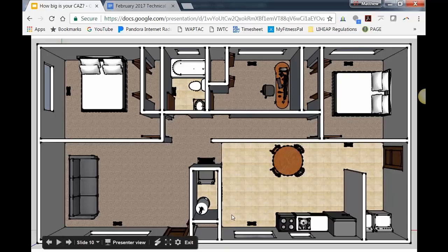So as an auditor, if you're walking into this house for the first time and this is the condition you find the house in, you don't get to modify stuff yet. You first have to do your worst case draft test, right? Because you got to make sure that when you leave tonight that the homeowners are safe. Just unfortunately, that's the burden we carry because of the knowledge we have. So you're going to test in. Also, it allows us to document that this was the state we found the house in.